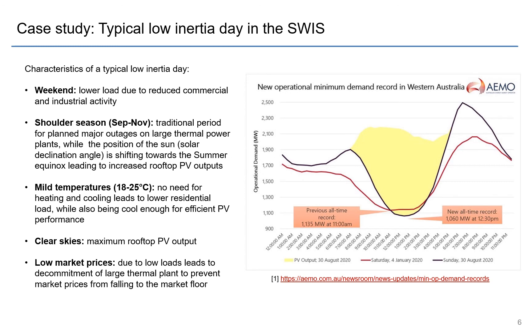Here's a picture of the lowest operational demand ever recorded in Western Australia. It occurred at 12:30 — peak sun. We've overlaid an estimate of rooftop PV output, and you can see that the actual underlying load was significantly higher, but rooftop PV ate up a large portion of it, producing a massive duck curve effect.